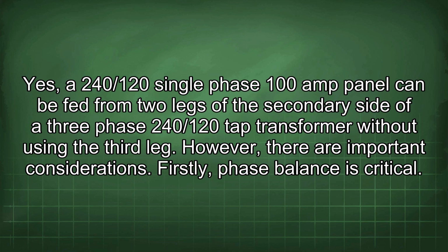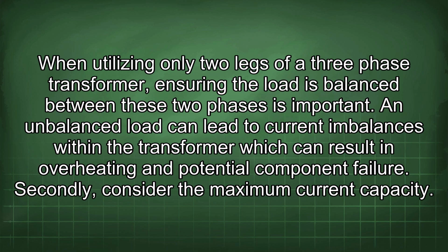Firstly, phase balance is critical. When utilizing only two legs of a three-phase transformer, ensuring the load is balanced between these two phases is important. An unbalanced load can lead to current imbalances within the transformer, which can result in overheating and potential component failure.